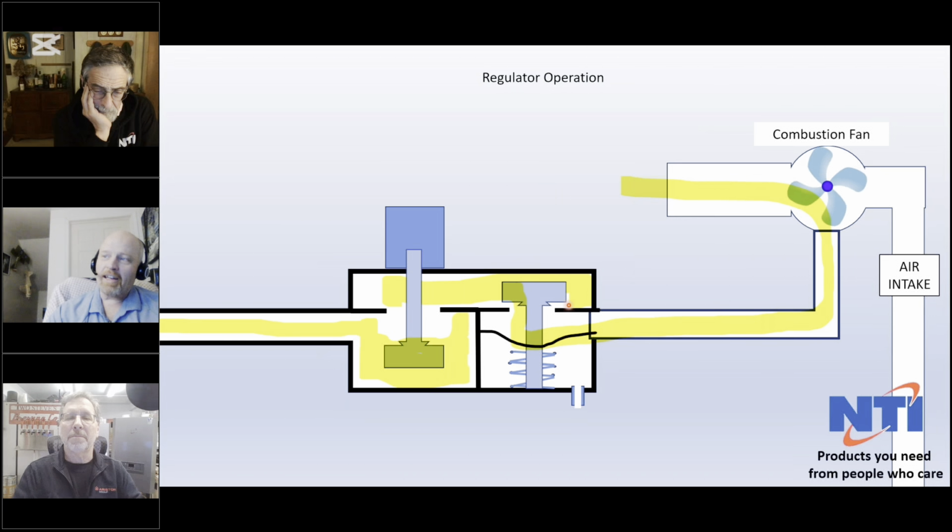So my advice to that contractor was to clean the boiler thoroughly, go through, and if you have to, tape off every wire. I didn't know about thumb gum, but I do now. So put some duct sealant on anything that could leak, and just make sure that all the air for that boiler comes from the outside world, because pool chemicals and condensing boilers are death. Absolutely.